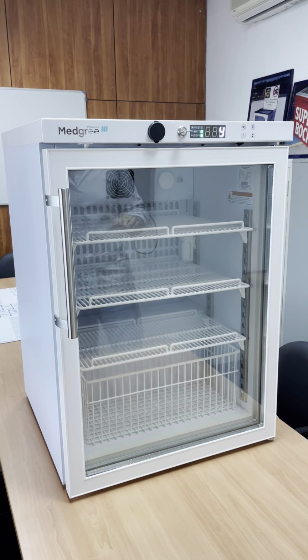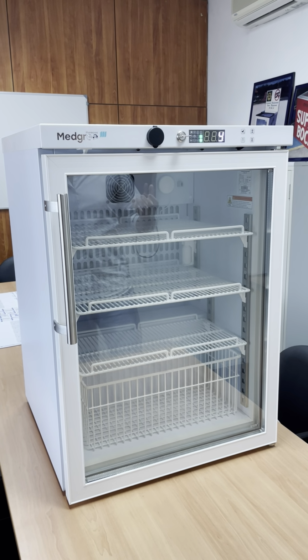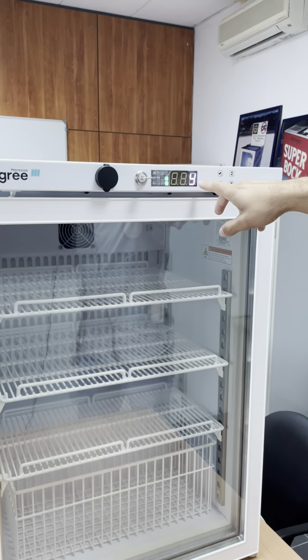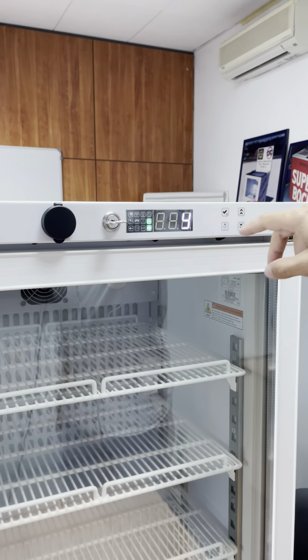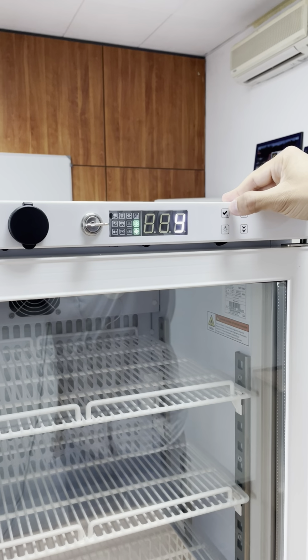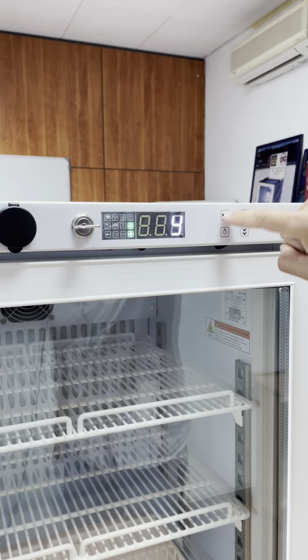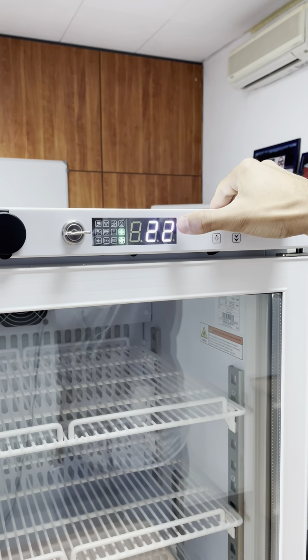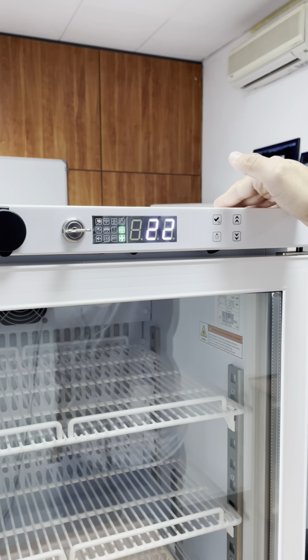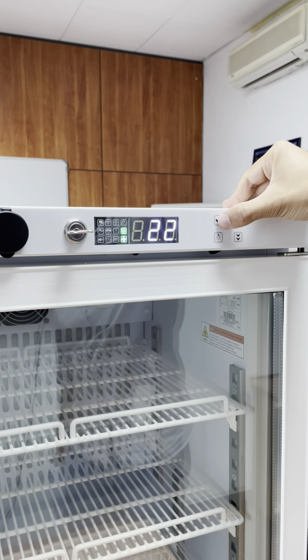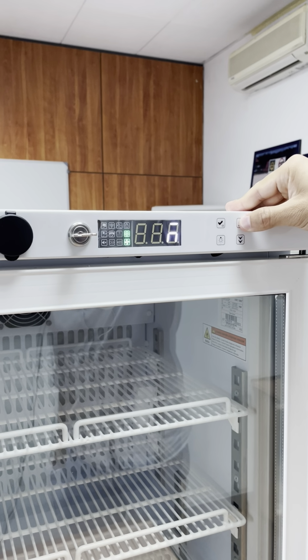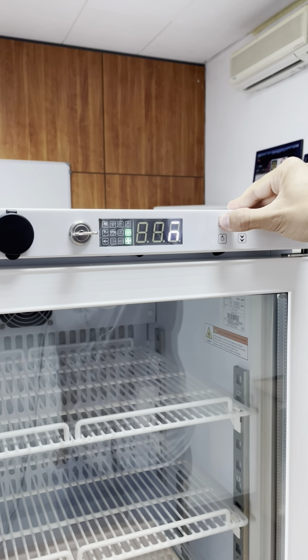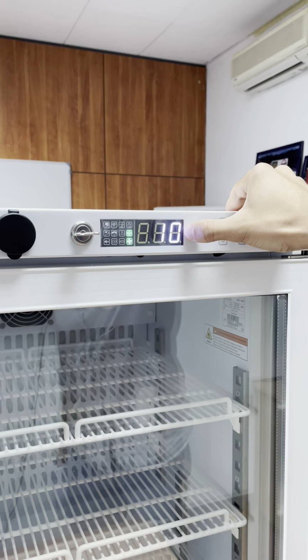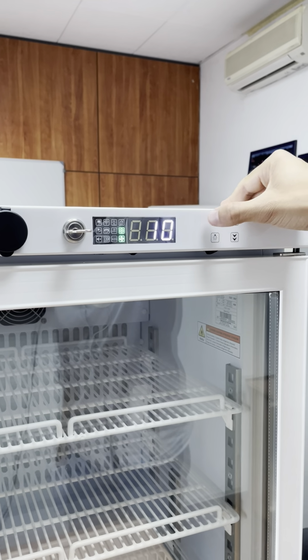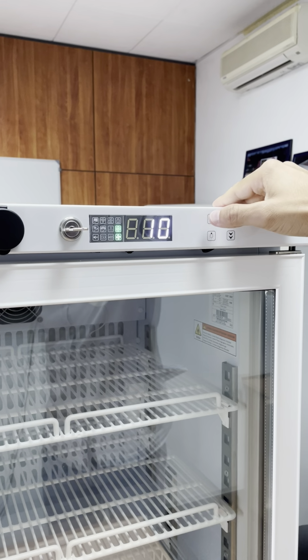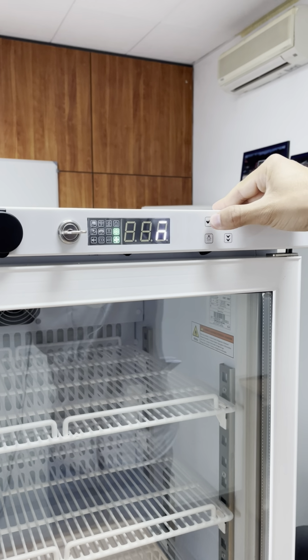The first thing that you need to do is to set up the date. So first you have the Y, that is for year. So you need to enter in the parameter by clicking in the first button on the left, and you set the year. In this case it's already 22, so it's okay. Then you confirm, and you pass for month. Month is 10, so we are in October. It's already correct because I previously set it. And then you confirm again.